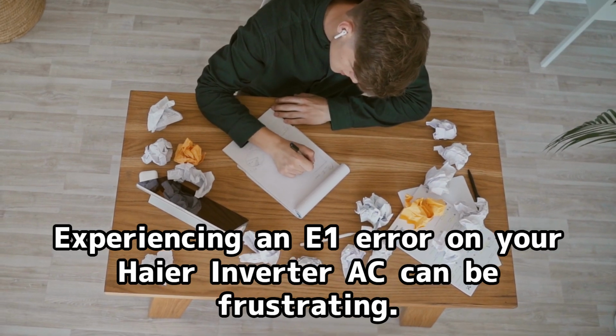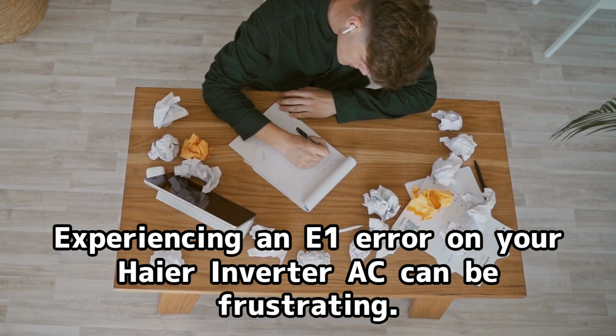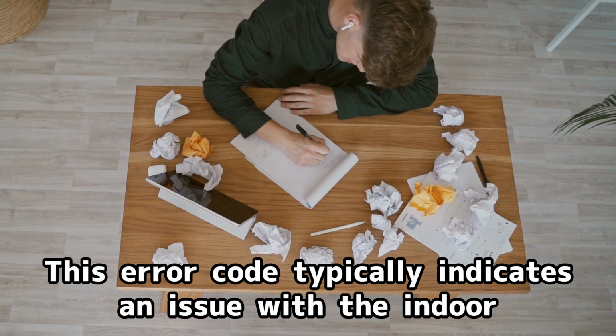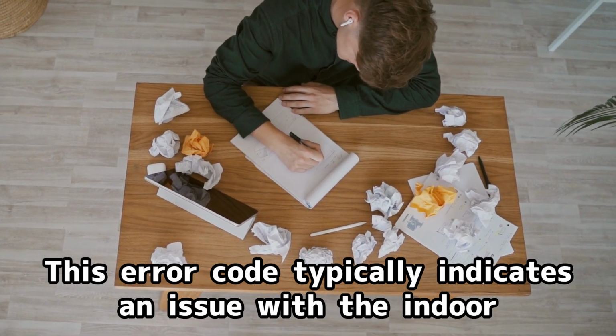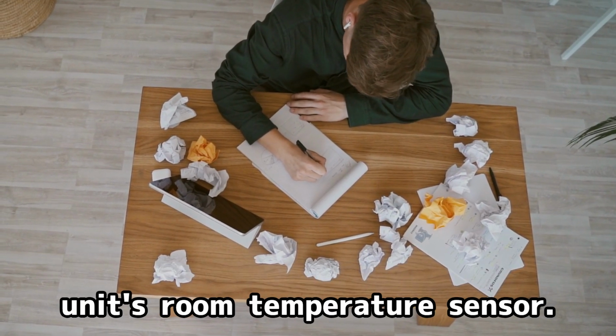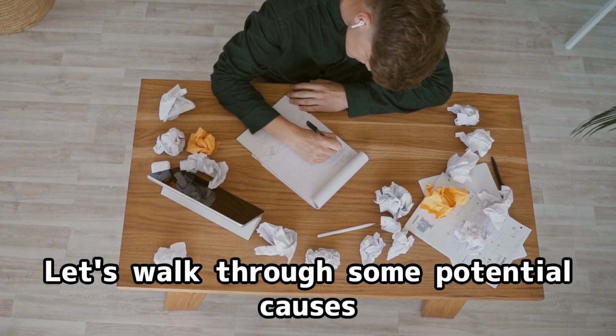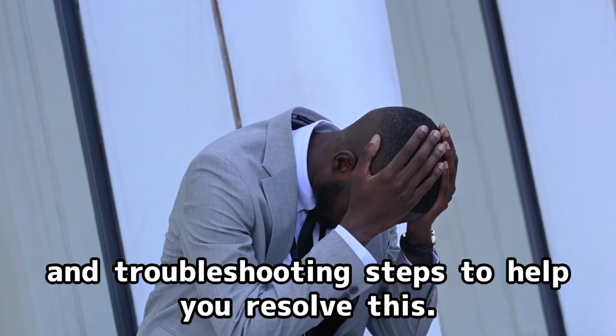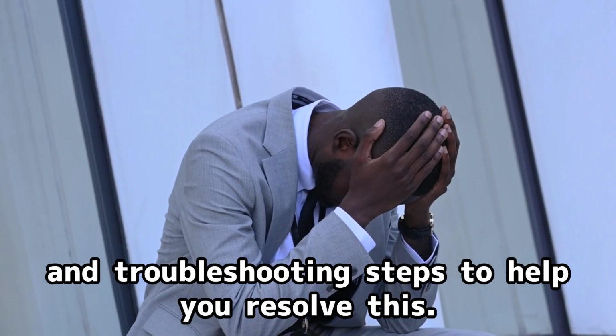Experiencing an E1 error on your Haier Inverter AC can be frustrating. This error code typically indicates an issue with the indoor unit's room temperature sensor. Let's walk through some potential causes and troubleshooting steps to help you resolve this.